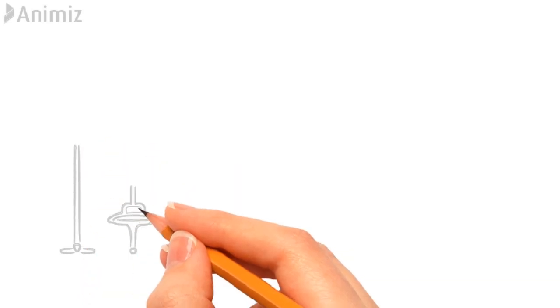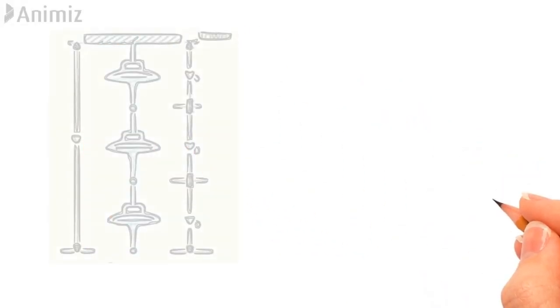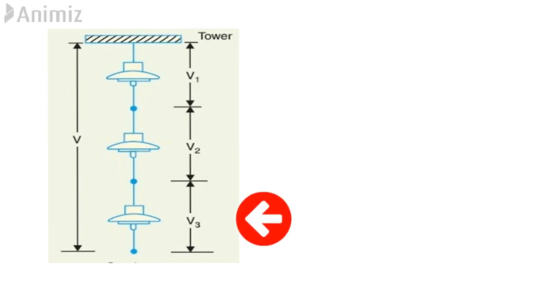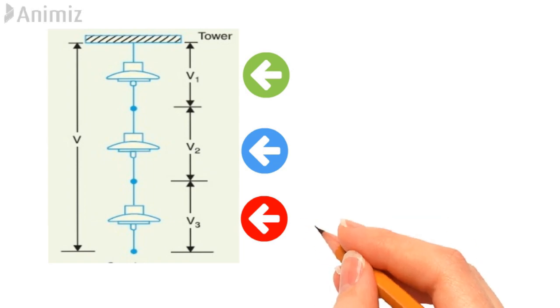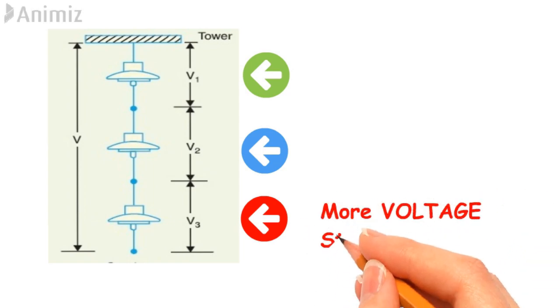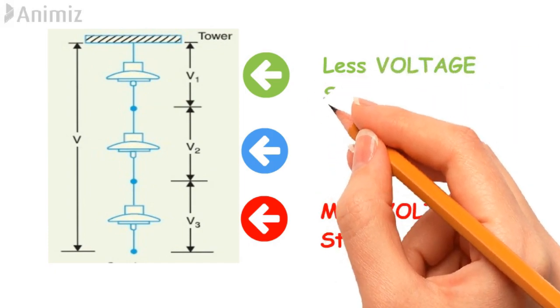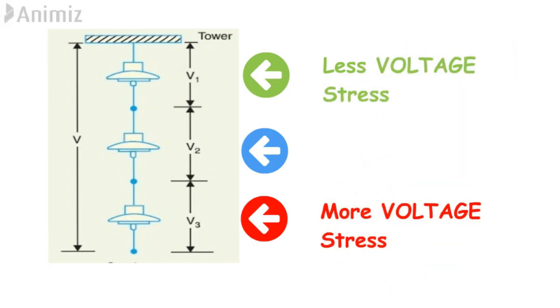One of the methods of equalizing the potential of suspended insulators of a string is grading the capacitance unit. In this method, voltages across each capacitor can be equalized by using discs with different capacitances. As we have seen, the insulator which is placed very near to the conductor experiences more voltage stress, so if we use different insulator plates with different capacitance values, it can be a solution to this problem.